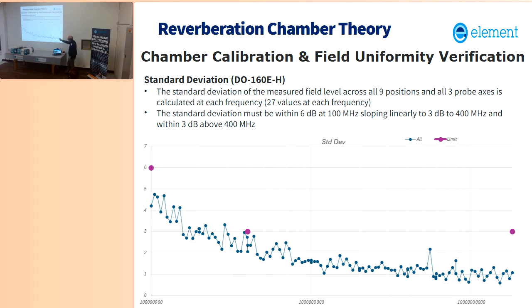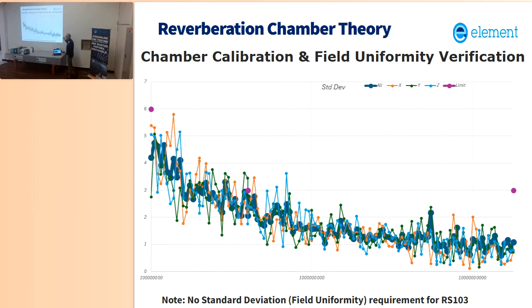So again, for all 27 positions, the standard deviation comes in nicely. This gets a little busy, but you also have to evaluate each axis. The 27 positions have to meet the requirement, but each axis has to be individually evaluated. And see how we've got a couple of frequencies that go above the limit down here at the low end? In any particular axis, you're allowed to have 2 frequencies per octave that fall out of the standard deviation requirement. So it's really hard to get every single axis in. It's next to impossible. It's not impossible, but it's hard to do.